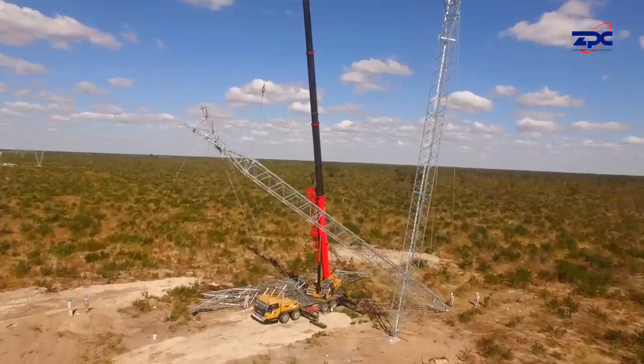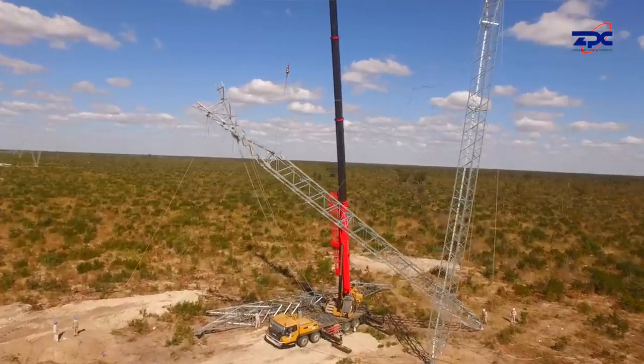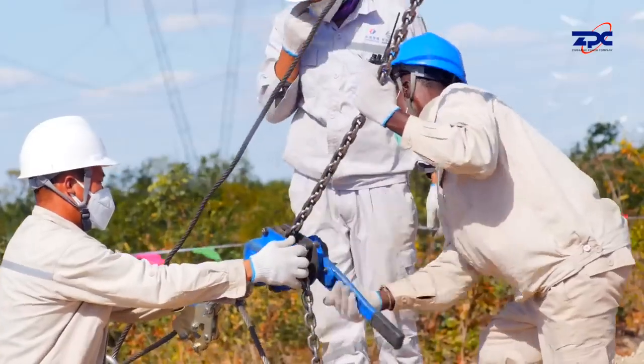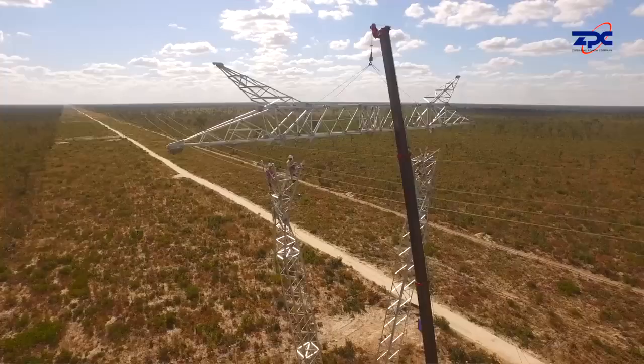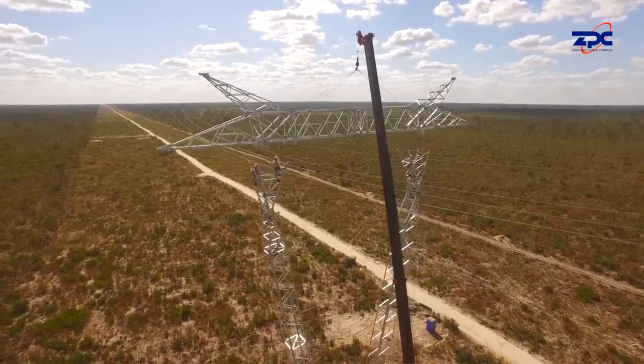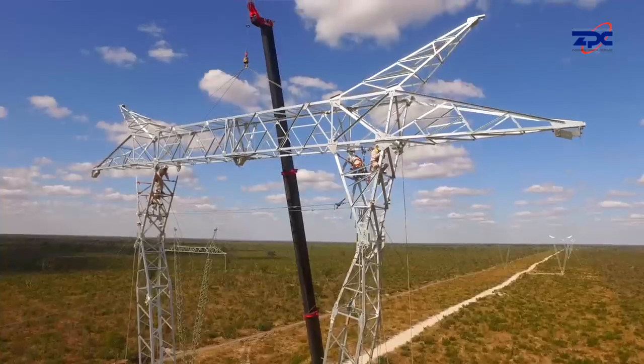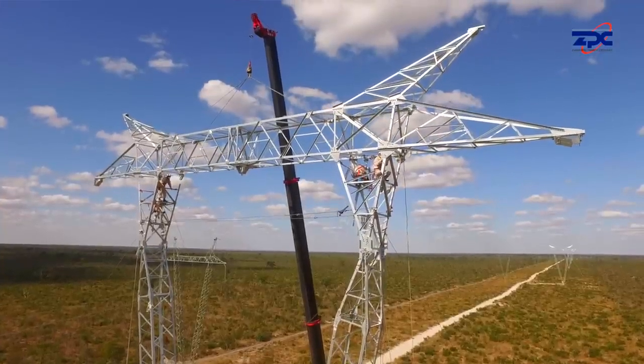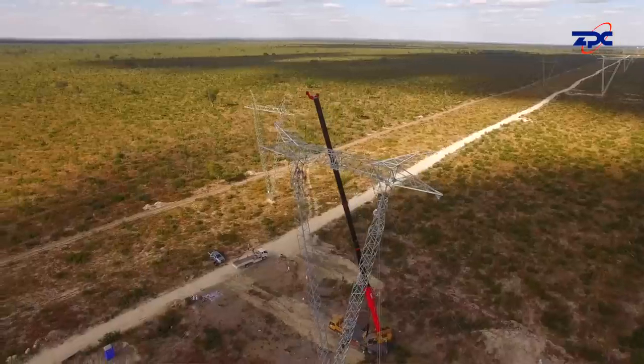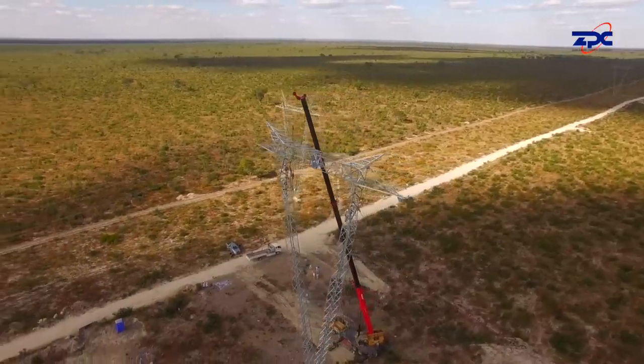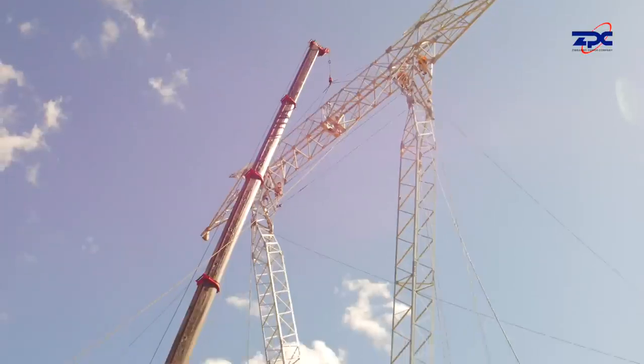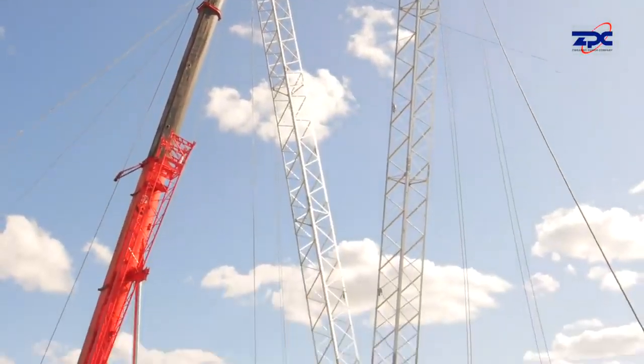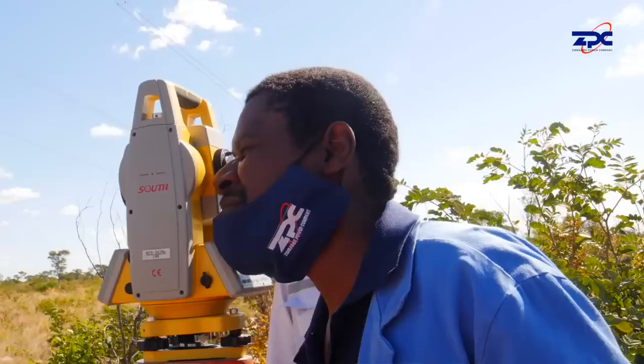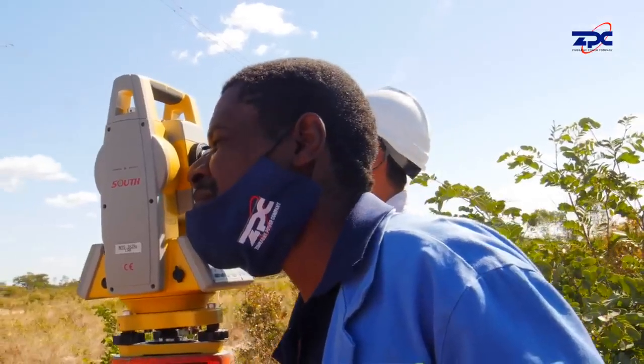The actual tower erection is done in 3 simple steps. We use the crane to lift one leg and support it with temporary stays. We do the same for the second leg. Finally, we connect the 2 legs with the cross arm and support the entire tower with permanent stay wires. Throughout the process, we continuously check for horizontal and vertical alignment using our trusted tool, the Total Station.